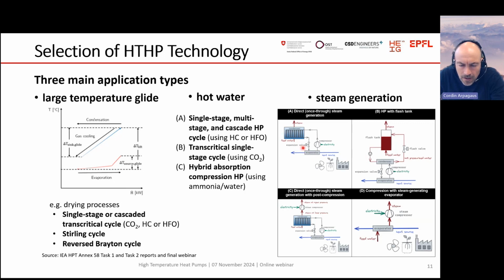We have a direct steam generation heat pump where the condenser is connected to the water, and it's generating steam in this condenser. Or you have a cycle with a flash tank where pressurized hot water is flashed, and so steam is generated. Or we have a combination with MVR to recompress a low pressure steam to a higher pressure steam. We call it sometimes a combined cycle. Or we have a concept where water is the only refrigerant, where the evaporator is at a high temperature so that water can be evaporated directly. So different applications mean different heat pump technologies or concepts.